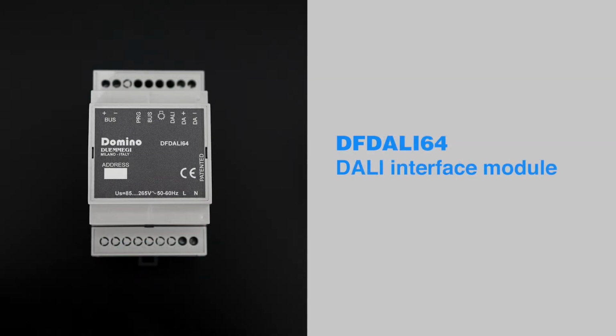The DFDALI64 module allows to control 64 DALI devices through the Domino bus. These are the main features: automatic addressing of connected DALI devices, up to 16 devices working at the same time or broadcast, a function for the automatic regulation of the light through the DFLS Domino sensor.